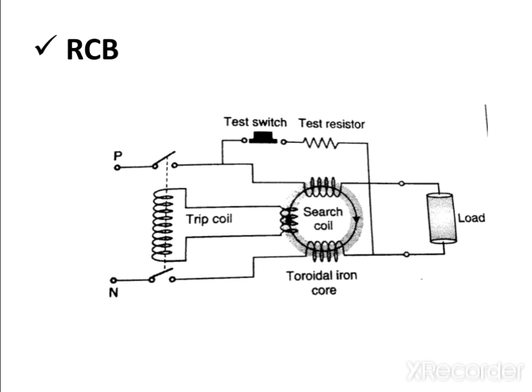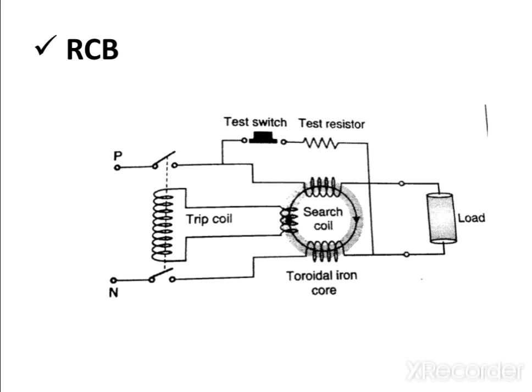If a fault occurs at the load side, then the current through the phase is 5 ampere and this comes through the search coil and through the load. Out of the 5 ampere, 3 ampere current goes to the leakage and 2 ampere continues to flow through the toroidal iron core and neutral. So there is a difference between phase and neutral current, that is, 5 ampere we send and there is a leakage of 3 ampere. So the difference between the two currents is 3 ampere. Therefore the trip coil operates and this will send the signal to the circuit breaker.